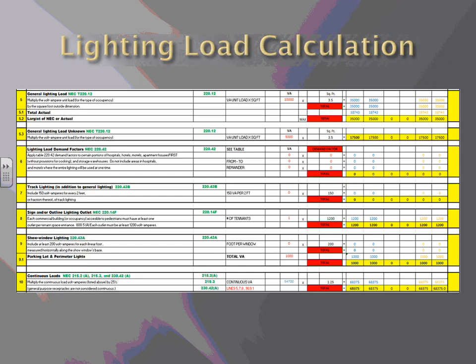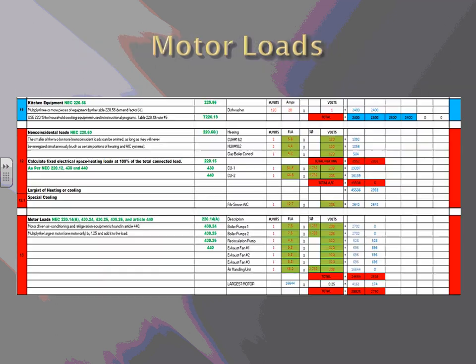we take per NEC table 220.12, we had 10,000 square feet at 3.5 per square foot, giving us 35,000 VA. We had an actual of about 18,000 VA. We take the highest of the two, giving us 35,000 VA. And then we did a general lighting expansion of 5,000, giving us another 17.5 kVA. We had an indoor sign at 1,200 volt amps, and then we had parking lot at 1,000 volt amps. Multiplied by 1.25 as continuous loads, giving us a total of 68 kVA for the lighting.